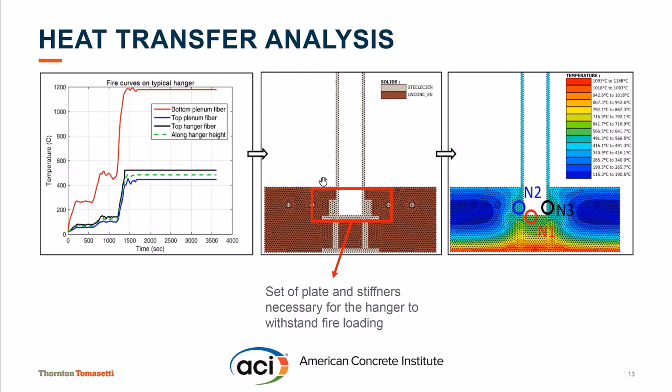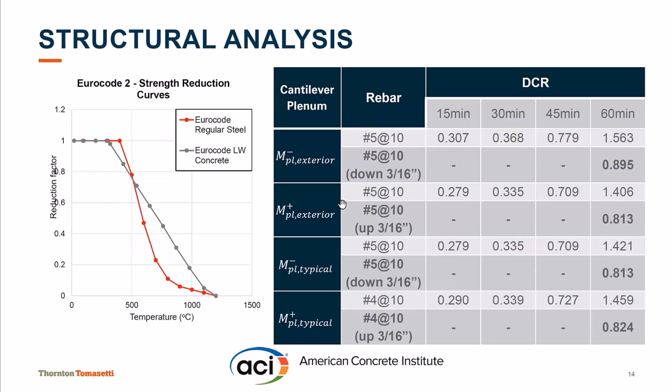So this was our first design recommendation: adding an additional plate and a pair of stiffeners to each steel tube next to the exhausts, and adding fireproofing on the tube surfaces exposed to higher temperatures during the fire loads.